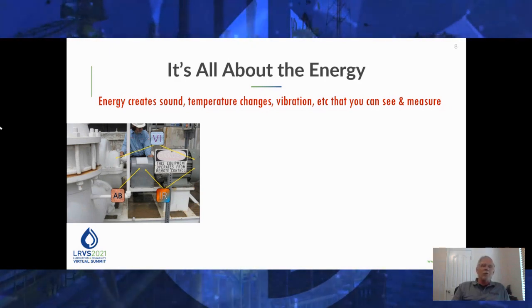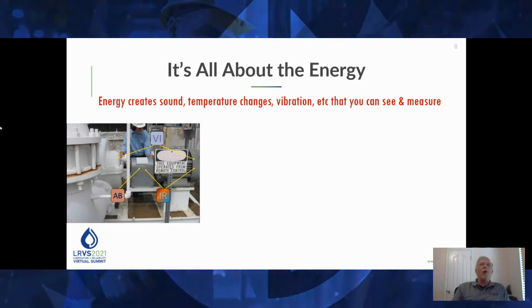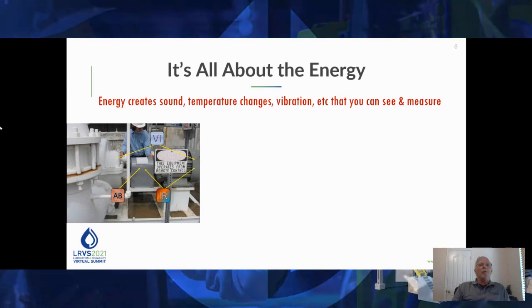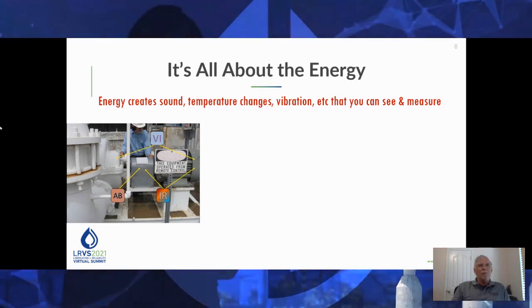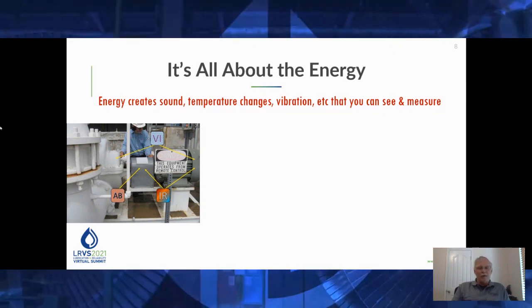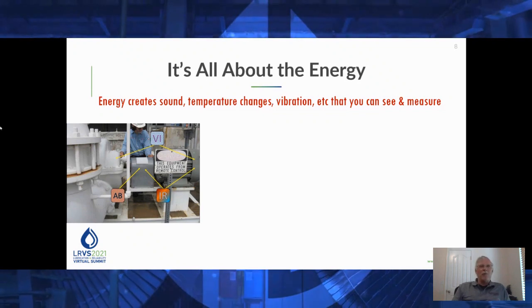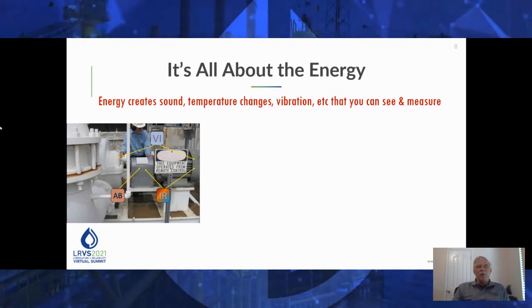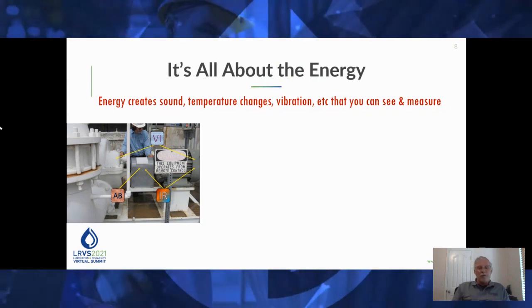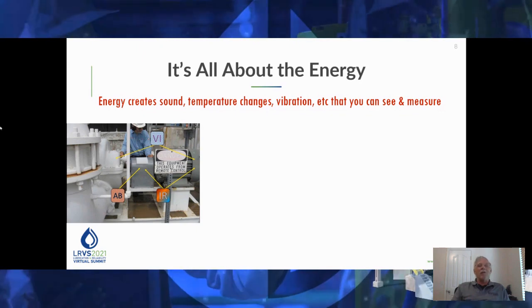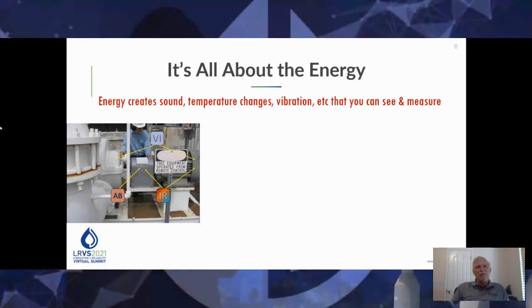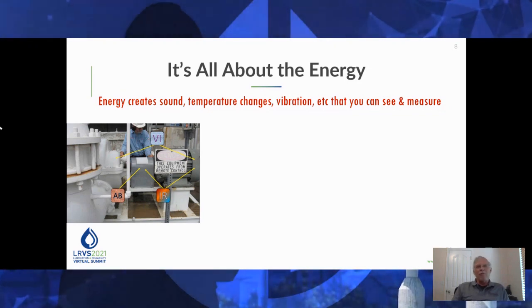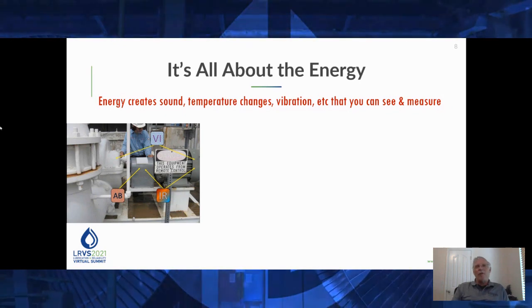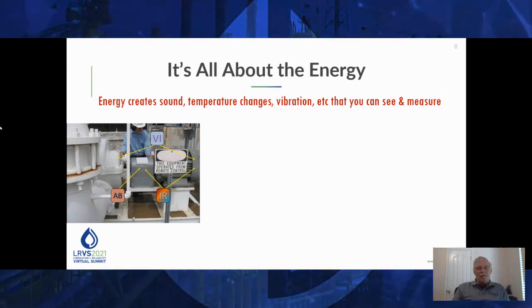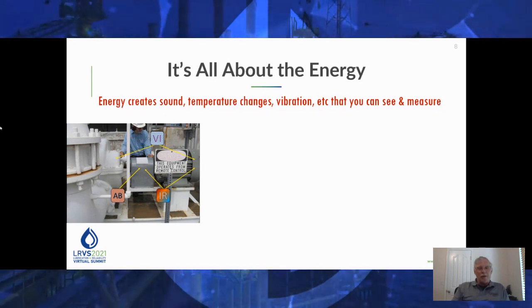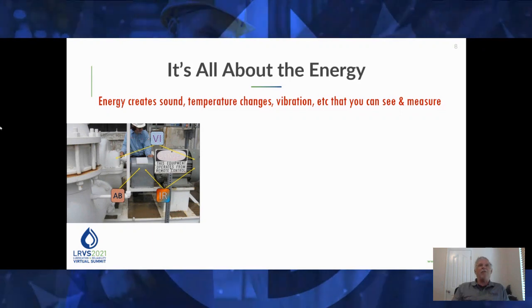Again, you can learn a lot from trending by taking all of these things combined. Okay? Infrared will tell you if the energy is going in places you don't want it. Bearings should not heat up. Or the two bearings on a particular motor shouldn't be that much difference in temperature. So if one is cold and the other one is hot, there's something to look at. If the bearing on the non-drive end is hot and the coupling is hot, and you've got vibrations on the motor, but you don't have vibrations on the pump, you combine all that and you could probably say, I've either got a bearing problem or I've got a coupling problem that has manifested itself in that bearing.